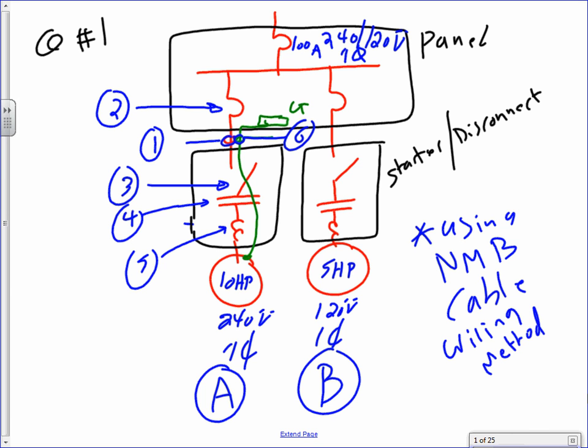Here's what you guys are looking at. That box that disconnects, looking at a disconnect like that. When you open it, and I'm sure you wired a few of them, what you're looking at right there is a disconnect to disconnect the system, a circuit breaker to protect it as the overcurrent device, a contactor, that's a controller, and an overload. Did you see that? That's what you buy to power major equipment. This is a 100 amp 3-phase. They have a smaller version of the single phase part. So this box that you're looking at here, Matt, is really that box here.